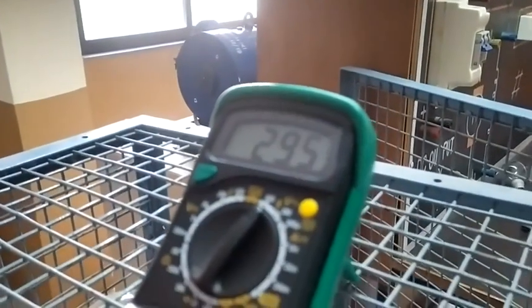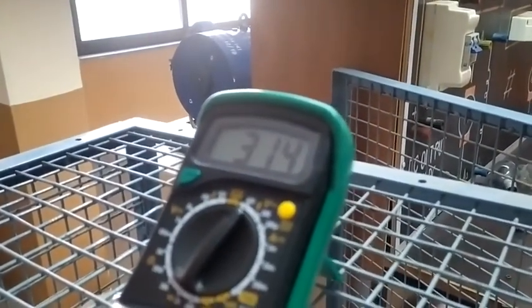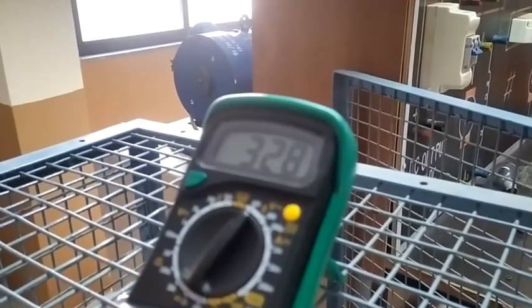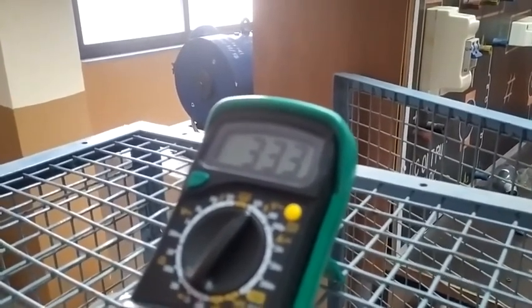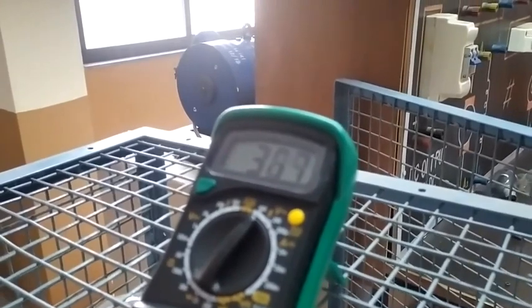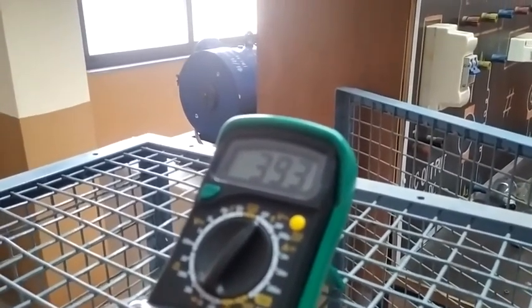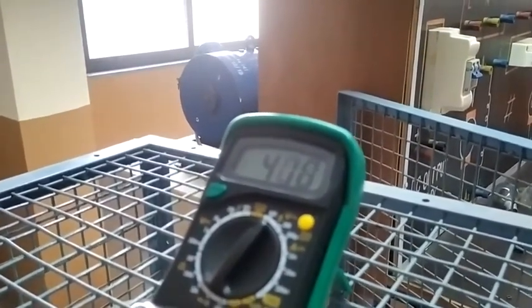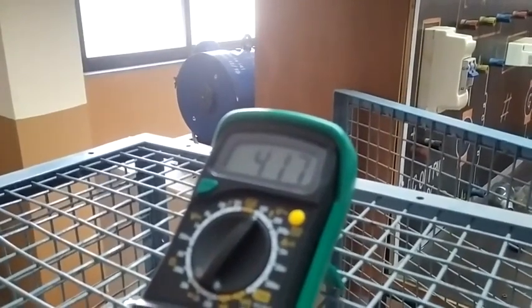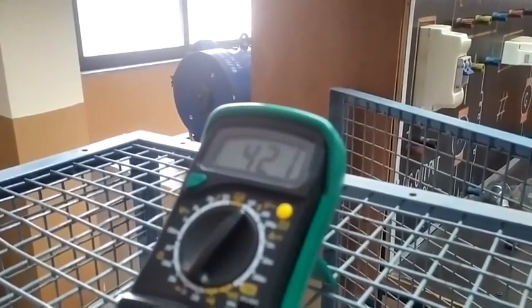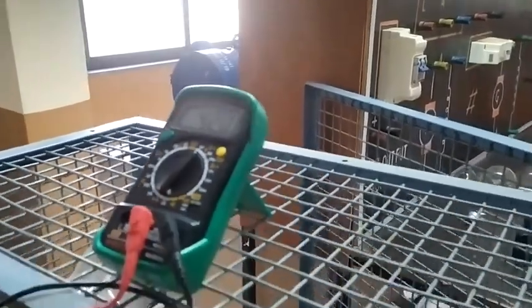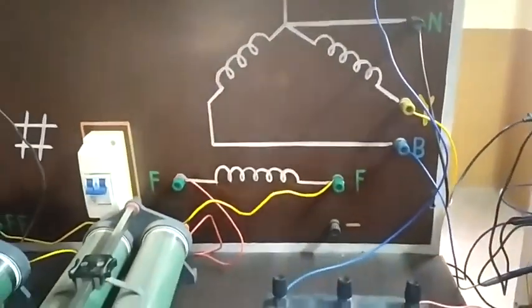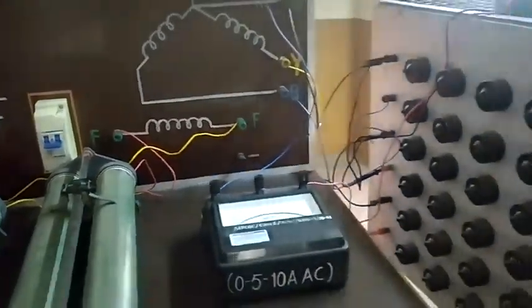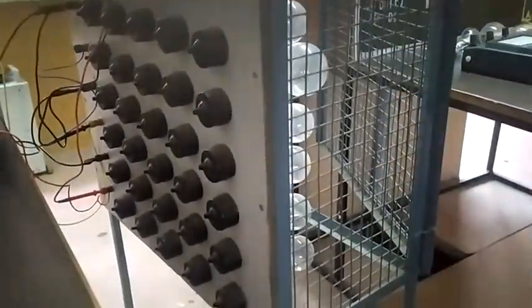Now I am varying the rheostat of the field circuit of the generator so that I can obtain the rated voltage of the alternator. My rated voltage of the alternator is about 415 volt. So by using the field rheostat, I am adjusting to the rated voltage. Now I got near about 420. Now you should apply the balanced load system for getting the voltage regulation. Now these are for a three phase balanced load system. I am switching on one by one.